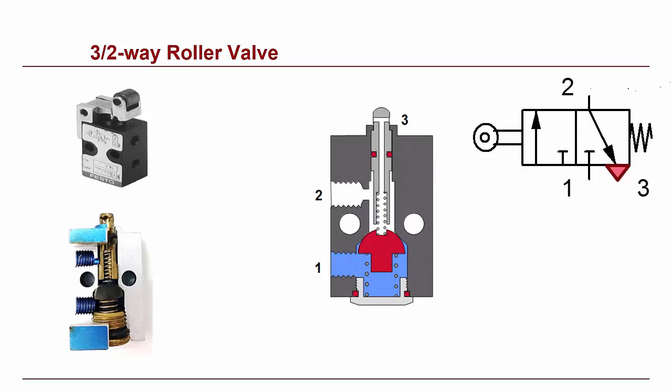When the roller valve is not activated, compressed air supply to port 1 is blocked, but port 2 and 3 are connected. That is, air can travel freely between the two ports. Note that port 3 is normally an exhaust port, air escaped to atmosphere through this port.